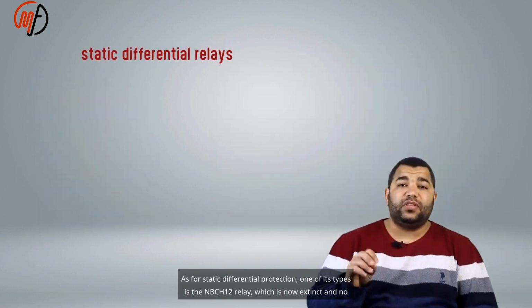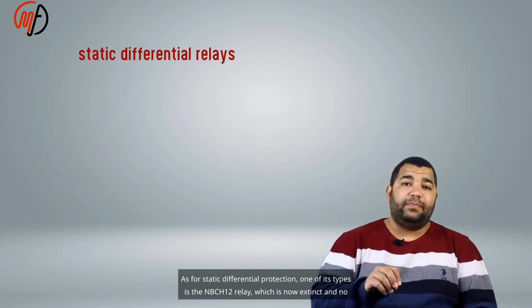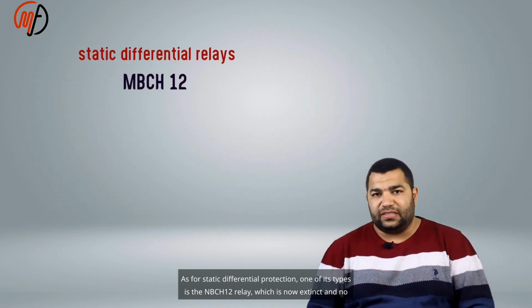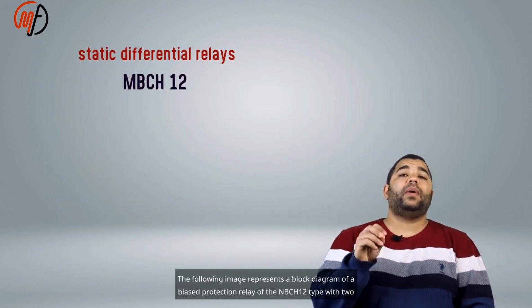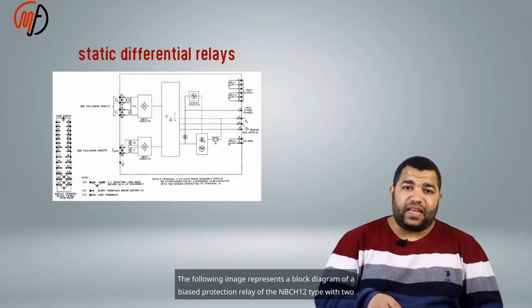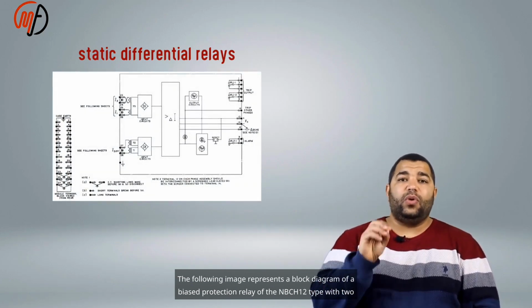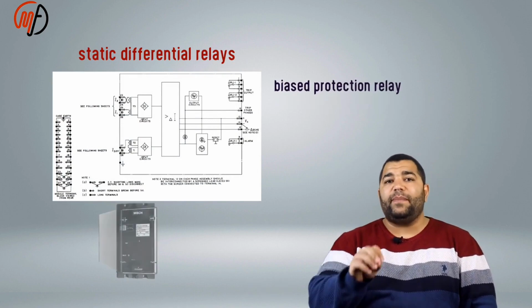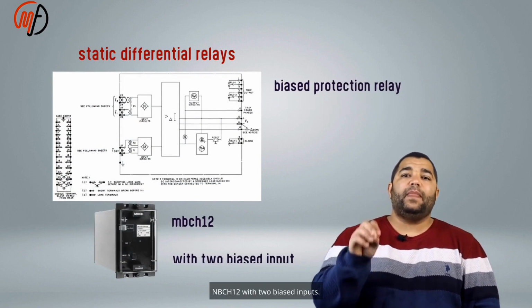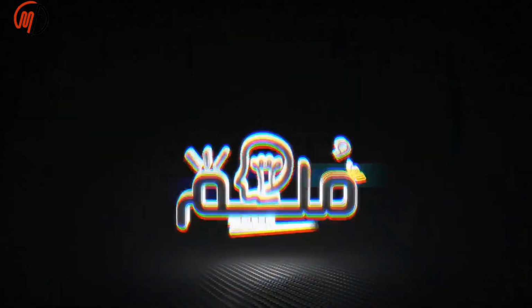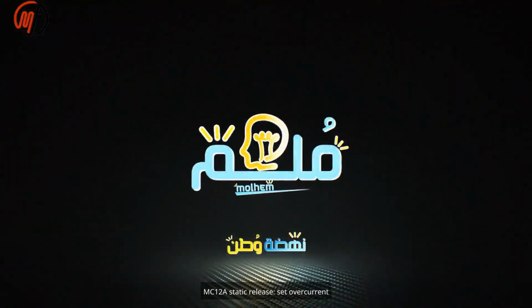As for static differential protection, one of its types is the MBCH12 relay, which is now extinct and no longer exists. The following image represents a block diagram of a biased protection relay of the MBCH12 type with two biased inputs. MC12A static relay, overcurrent setting.